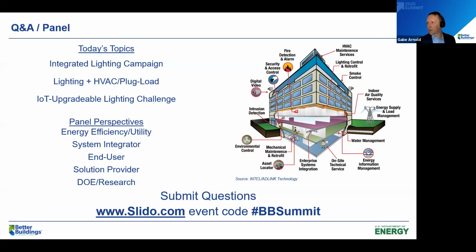We have found that it takes a long time to go from standby temp to occupied temp, and we get complaints. That question gets brought up all the time, and it's a great question. Every building is going to be different, depends on what the building envelope is and how much thermal mass you can keep in the building. What I've found is that most of the time, if your AC system works correctly, even if it's warm in a space and people walk in and it comes on, they don't complain. There are some spaces that are a problem, and we change the controls based on those specific problems as opposed to changing it globally and giving up all the savings. So that's pretty much the answer - once you go to a system where you can control everything, you have to actually control everything and not do it as a global override.